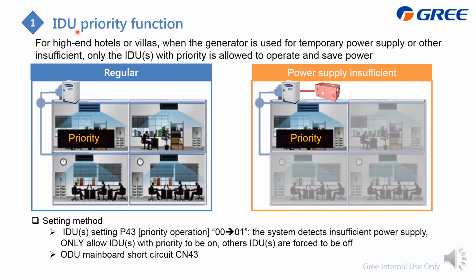And also the same, this system supports the indoor unit priority function, which means if you set the indoor unit with the priority and the outdoor unit has already activated the priority operation, then the system will only allow the indoor unit with the priority to operate. For example, if the power supply is insufficient, you just use this power generator for the power, and then you just allow your appointed indoor unit to operate. So you can set this function just like this.